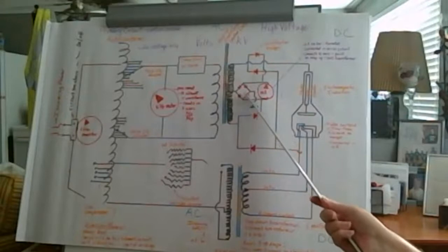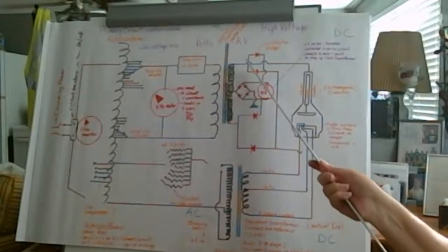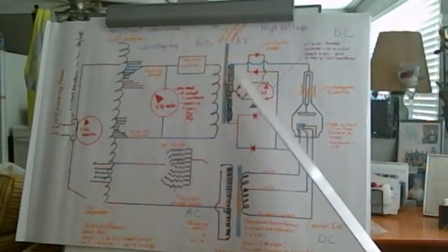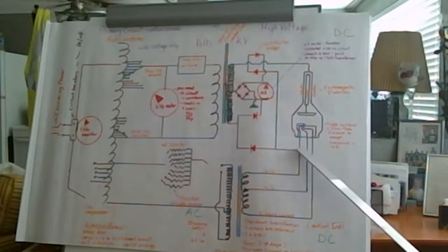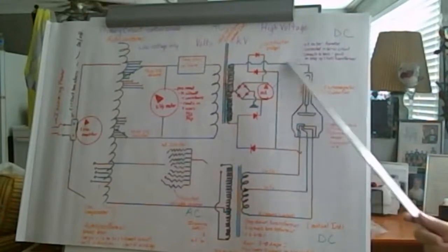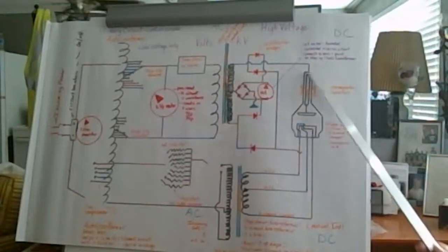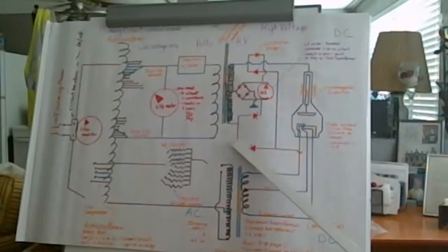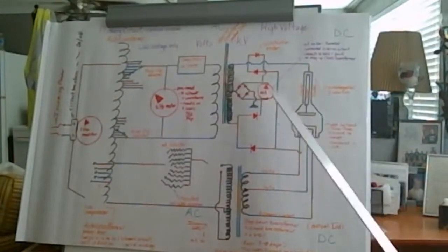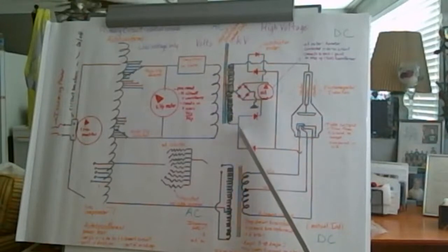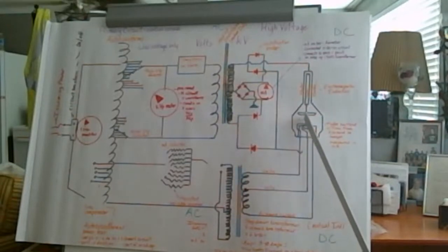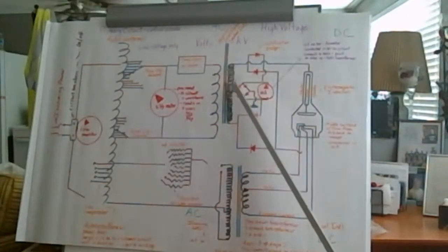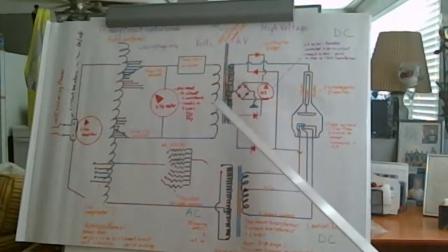Here we have our rectifiers, rectification bridges all along here. If you notice, we have lines that run here and run completely down and around. This secondary side is our high voltage side, and the power from this secondary side is fed into and through the X-ray tube and back out to that secondary side again. That's important.